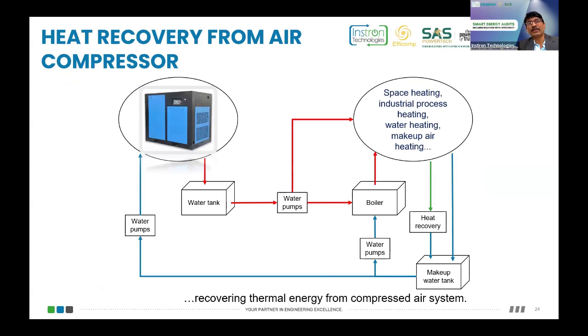Another example of compressed air system CO2 reduction is heat recovery. Generally, most people don't know that the compressor, as I said earlier, is one of the least efficient utilities. The main reason is that whatever air we get at the output is only 15% of the electrical energy we have given at the motor side as 100%. So around 7 HP is lost during that activity. That 7 HP is actually being lost as heat.